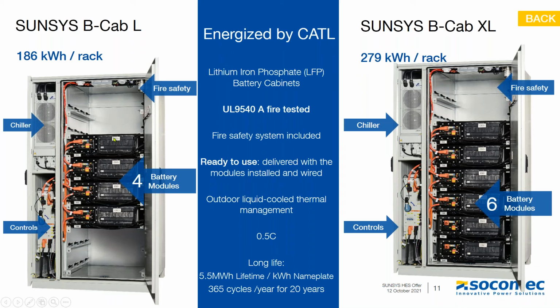So just like PV modules, battery modules in series, voltage adds. So this adds up into the low 800s. This adds up into the low 1100s. And these are the right voltage windows for their respective converters.